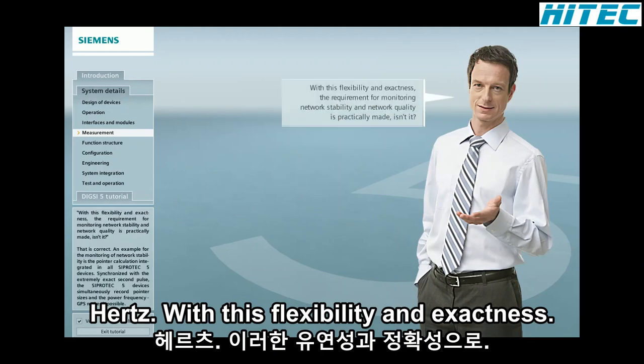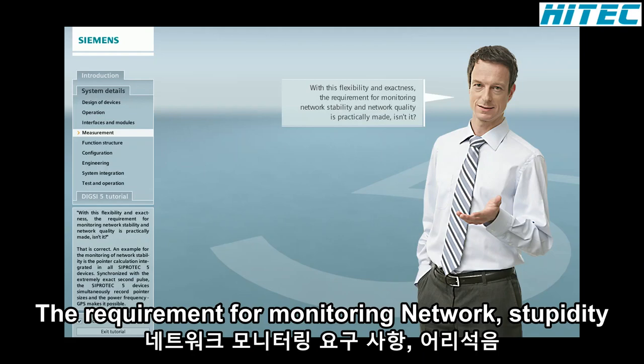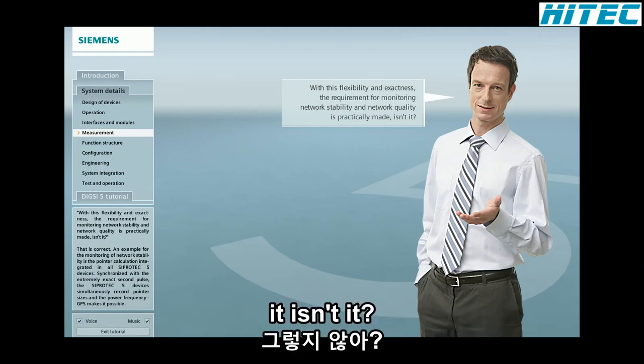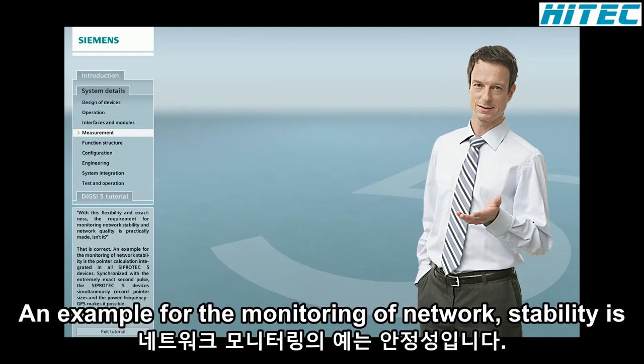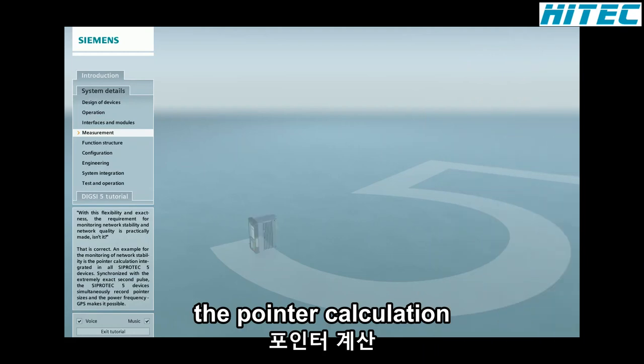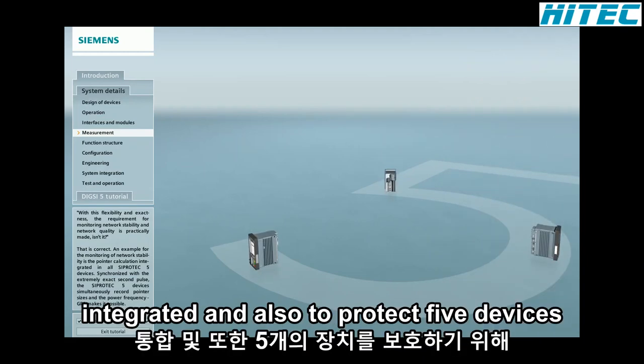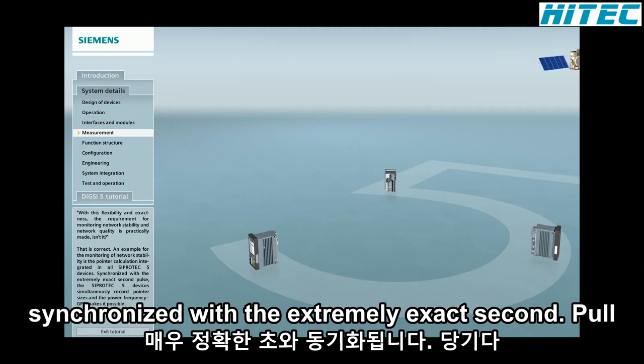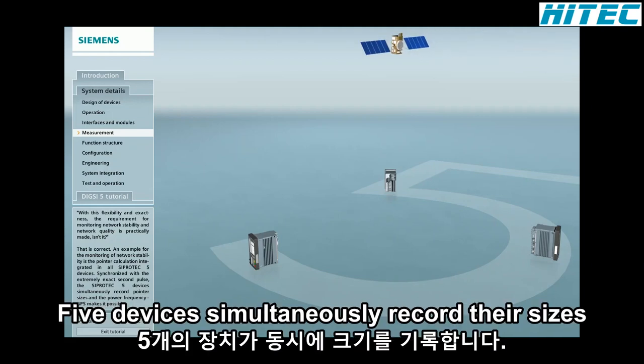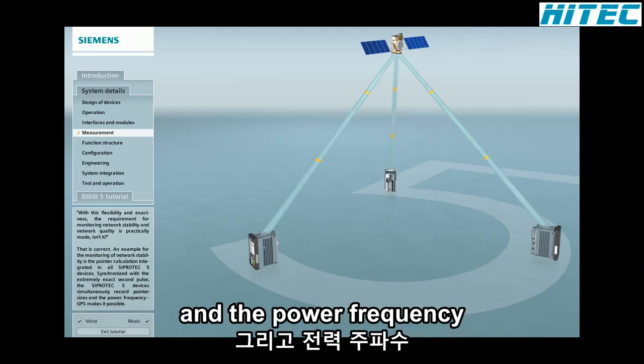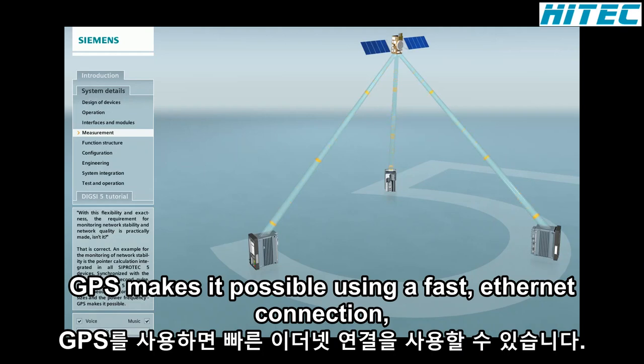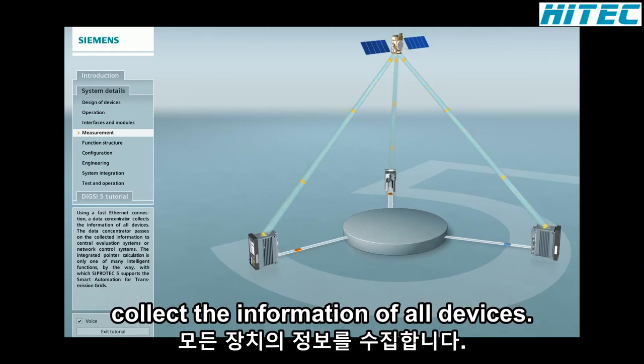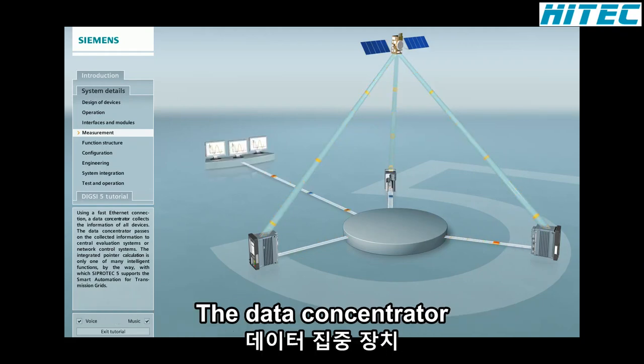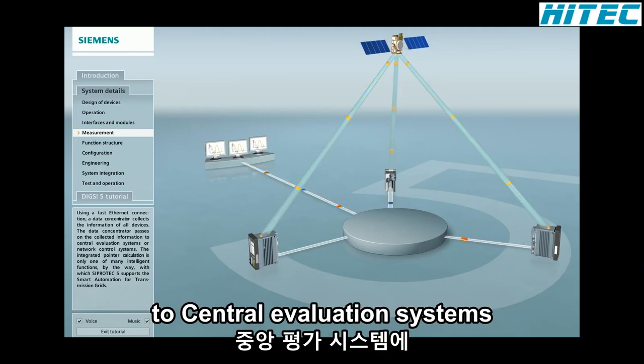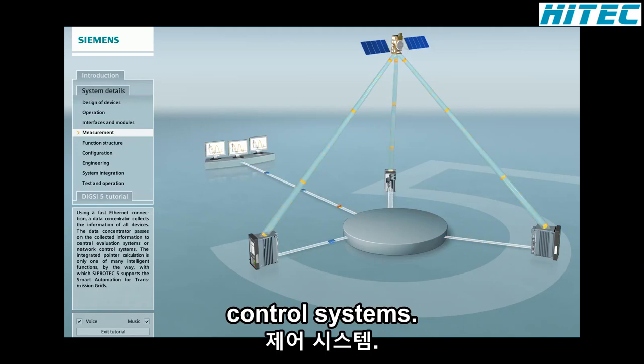With this flexibility and exactness, the requirement for monitoring network stability and network quality is practically made, isn't it? That is correct. An example for the monitoring of network stability is the pointer calculation integrated in all SIPROTEC 5 devices. Synchronized with the extremely exact second pulse, the SIPROTEC 5 devices simultaneously record pointer sizes and the power frequency. GPS makes it possible. Using a fast Ethernet connection, a data concentrator collects the information of all devices. The data concentrator passes on the collected information to central evaluation systems or network control systems.